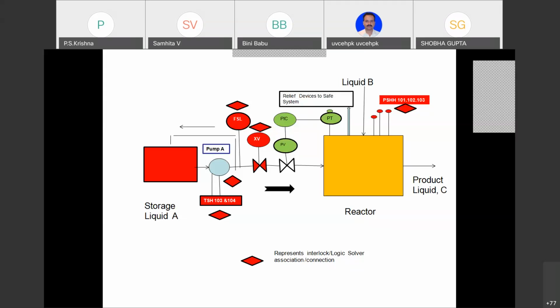Then they said, now let's come to flow. What happens if the flow is excessive? No, I don't want any excess flow. I want a normal flow. Why put excess flow? The reaction may become violent. So we can control. He said, okay, I'll control the flow. And then I'll do this controller, some magic. I'll do the algorithms and make it into a cascade controller so that it will take care of pressure and flow also. Okay, I won't confuse you people on that. Go for a cascade control or something.